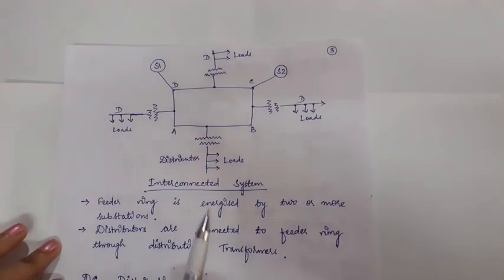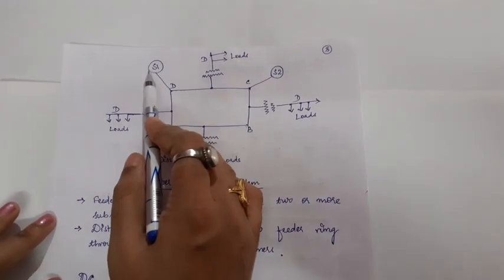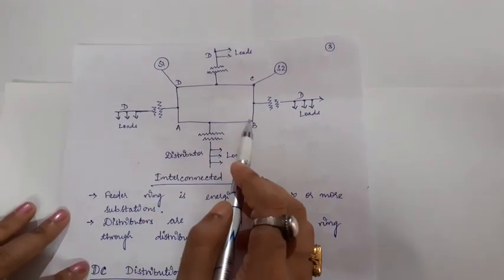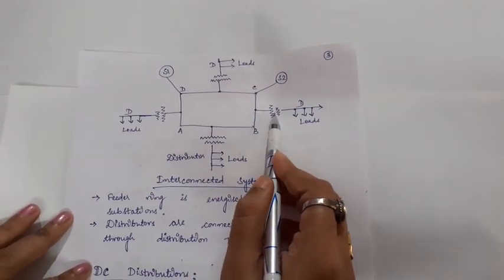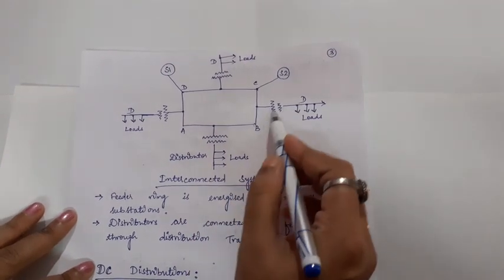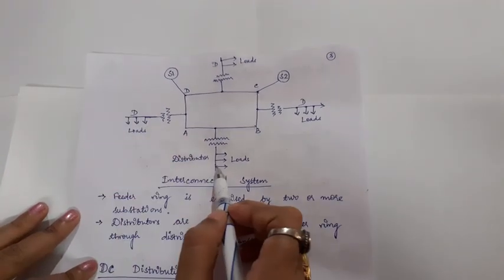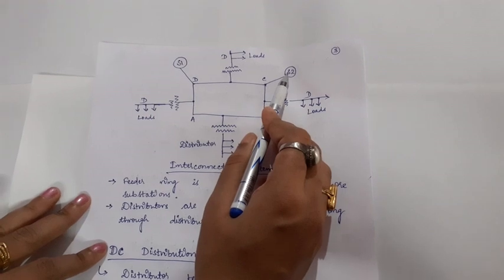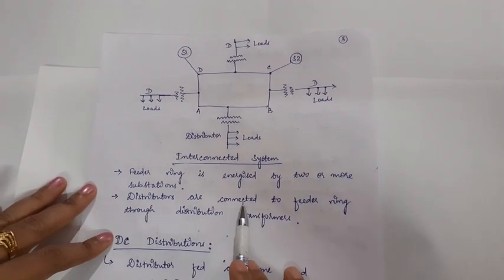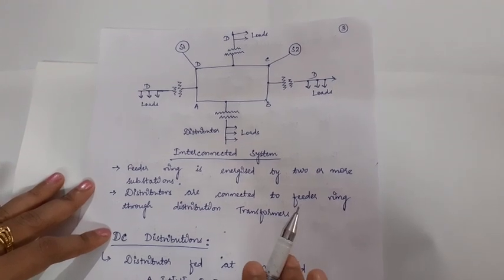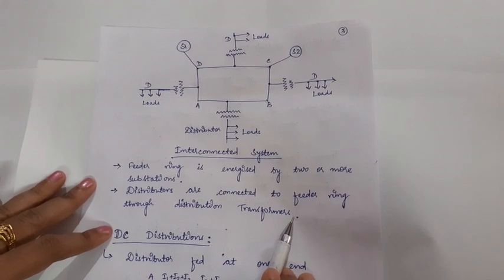In the interconnected system, the feeder ring is energized by two or more substations. Here S1 and S2 are the two substations which form a feeder ring. From the feeder ring, the distribution transformers are connected. On the secondary side of the distribution transformers, the distributor lines are there. From the distributors, tappings are taken to the service mains and finally to the consumer loads. More than two generating stations or substations are connected, and the distributors are connected to the feeder ring through the distribution transformers.